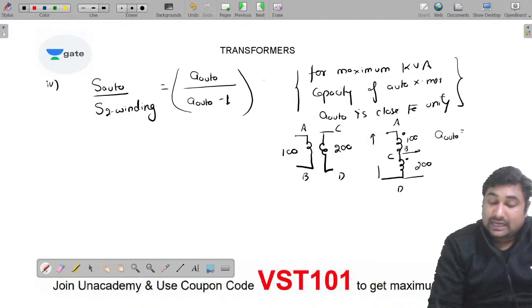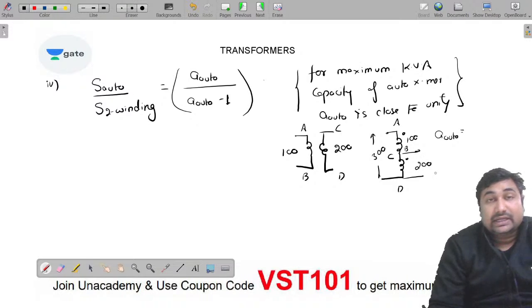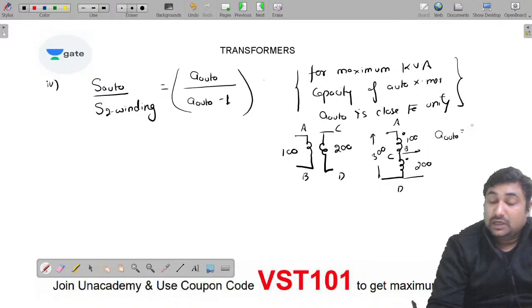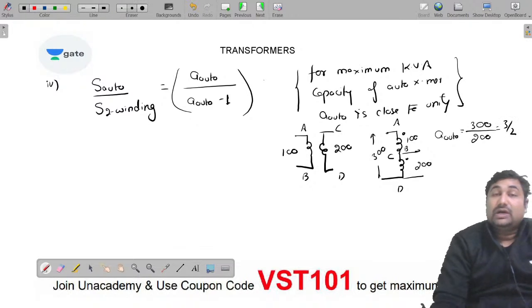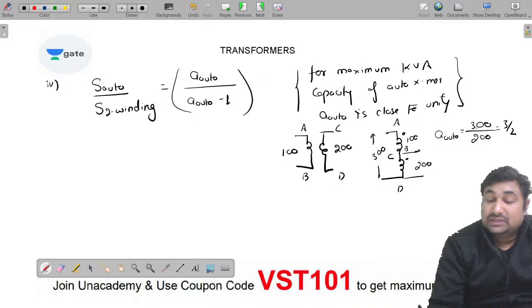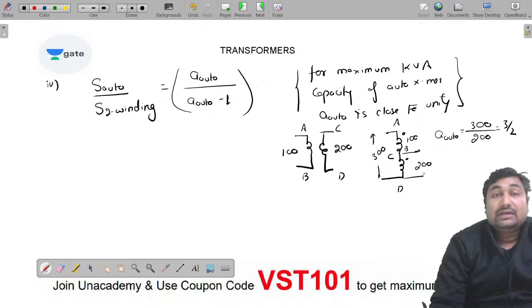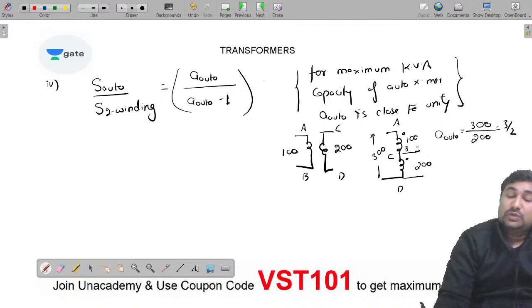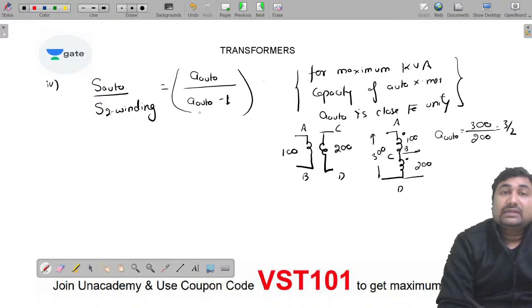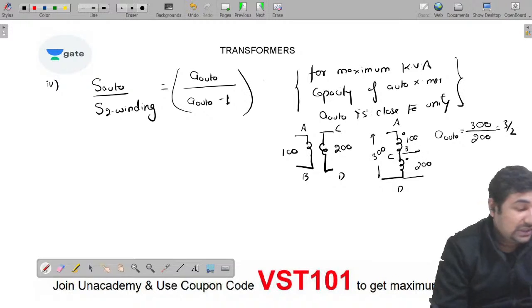Okay, so you can say, sir, the additive polarity shows this, the total voltage here will be 300 to 200. If you are using 300 to 100, then you are not getting full utilization of the connection. It means the kVA capacity will be lower. In order to have the maximum handling kVA capacity, you have to choose the winding connection in such a fashion that A auto should be close to unity. Now if you add these two, this will be 300 upon the HV side of the two winding transformer, that is 200. So if you are choosing 3 by 2, then you are going to get the maximum kVA capacity. Instead of this, if you are choosing, say, 300 by 100, then you are going to get lower kVA handling capacity. So we always use additive polarity in order to get the maximum kVA capacity, and A auto should be close to unity. Is it okay?